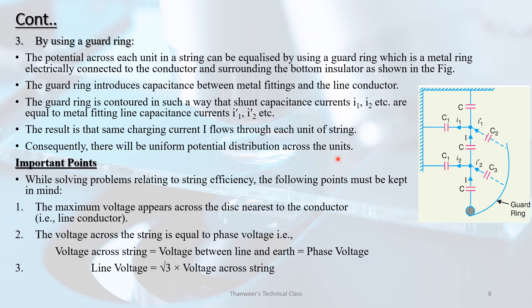Consequently, there will be uniform potential difference across the units. While solving problems relating to string efficiency, note that maximum voltage appears across the disk nearest to the conductor. The voltage across the string is equal to the phase voltage, i.e., line voltage divided by root 3, equals the voltage across the string.